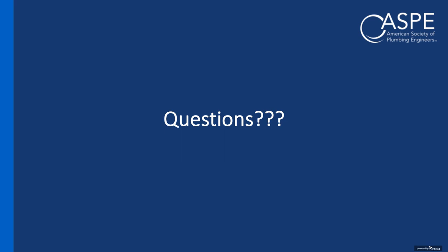Perfect. We're getting to the end of the hour here, so I think we'll just take about 2 or 3 more questions. Next question, Tom, are there any issues having different return temps on the TBV based on the branch use, aka kitchens versus restrooms on the same system? No, you just have to keep in mind that whatever setting you make on those balancing valves, that's what it's going to control to. So we have seen systems where they will have a different balancing valve in the kitchen for like a 140 return versus the primary recirc system that may be at 110 or 115 or something like that. That's fine.